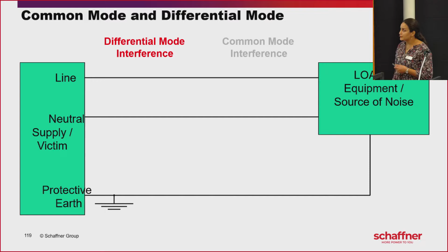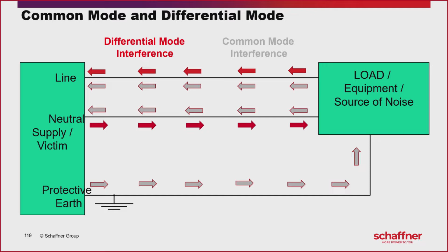Besides that, we also have the common mode current. We usually say the current takes the shortest path to Earth, but actually it takes the path with the lowest impedance. At lower frequencies, the differential mode is more present because the closest path to Earth is usually through the neutral. But at higher frequencies, the common mode is more present, and the filter should cover both.